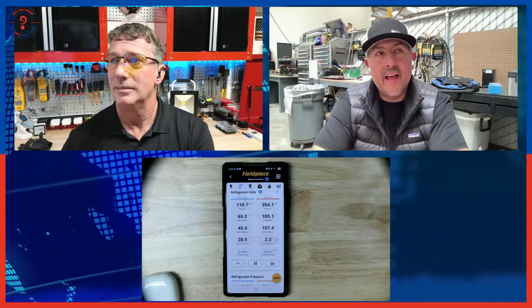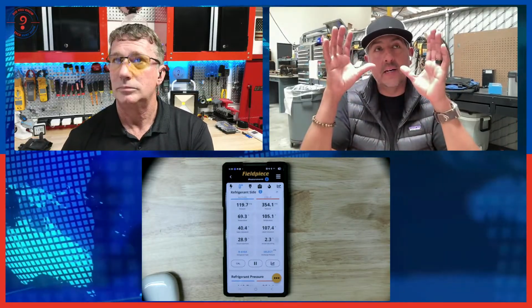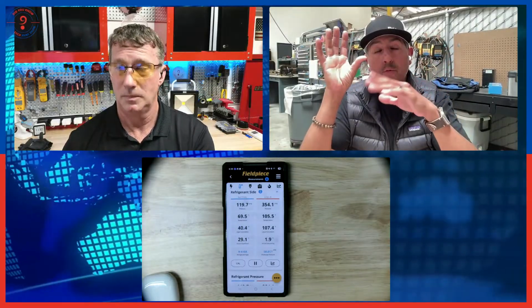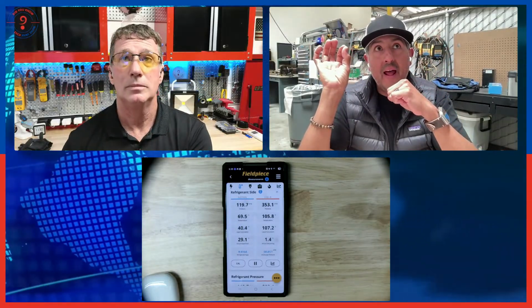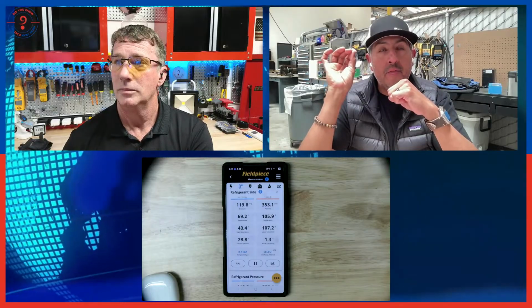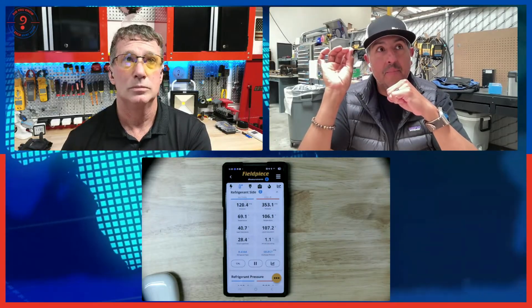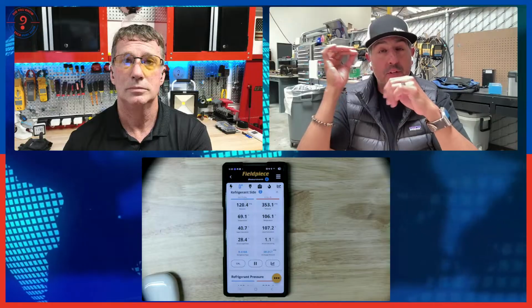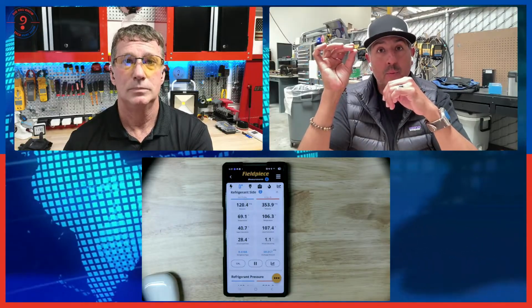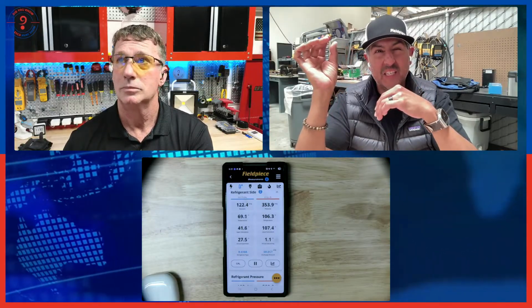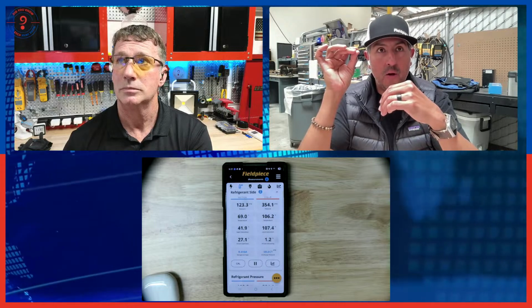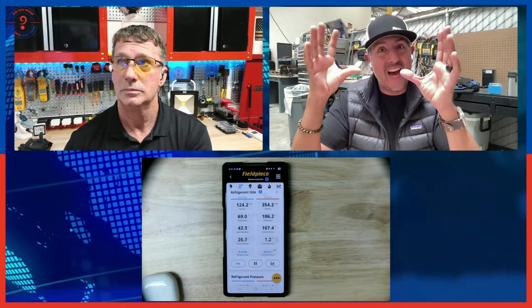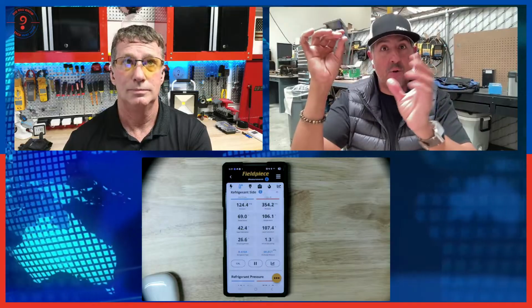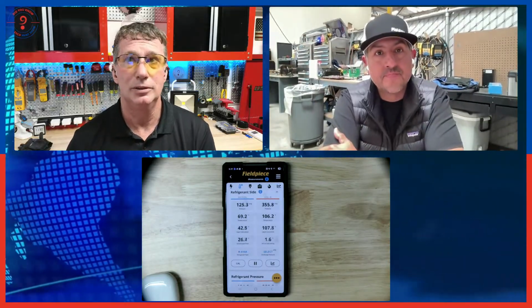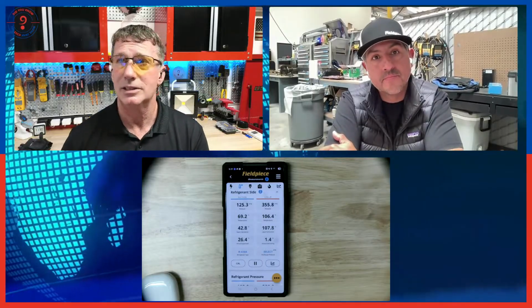Okay. Yeah, and in the field, there's that balance of being too close, being too far. Like if we're too far away, then the measurement can be affected by issues with the ductwork, right? Either static pressures or leakages, which isn't a true reflection of what's going on at the coil. So in the field, the technician has got to use their best judgment and just try to get in the best place.